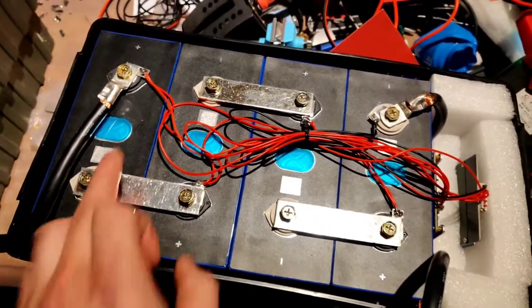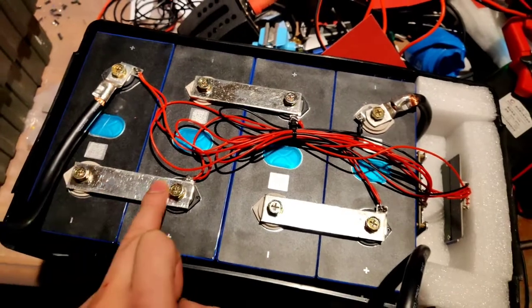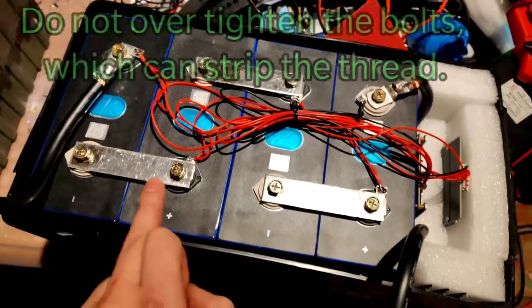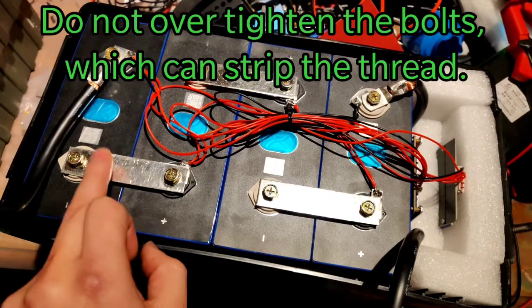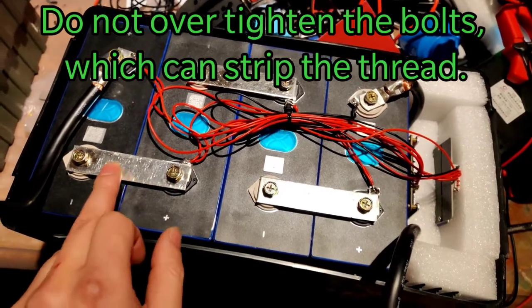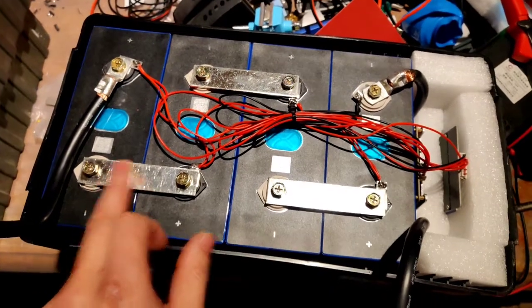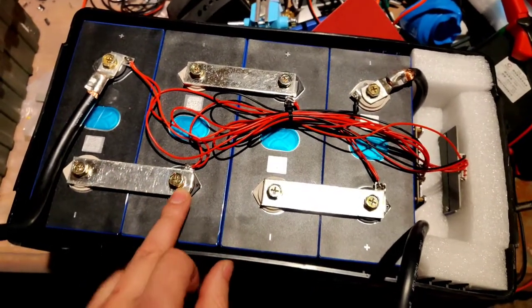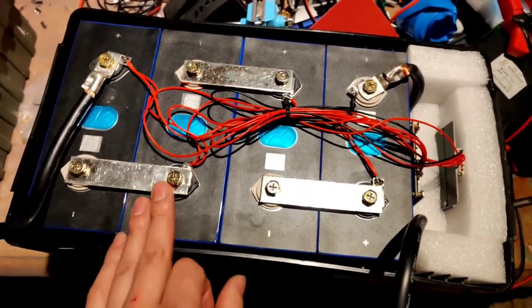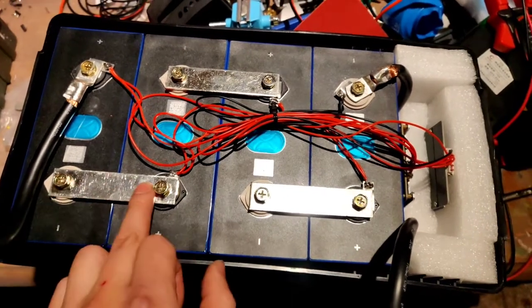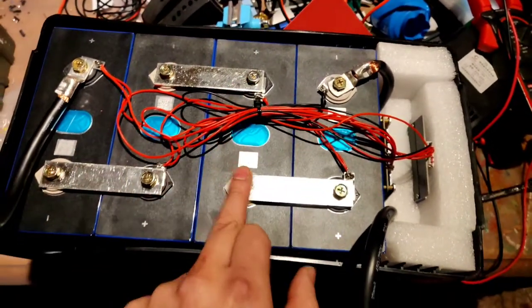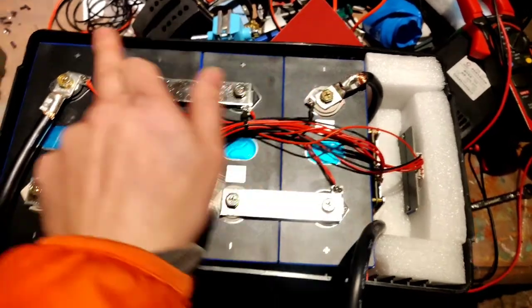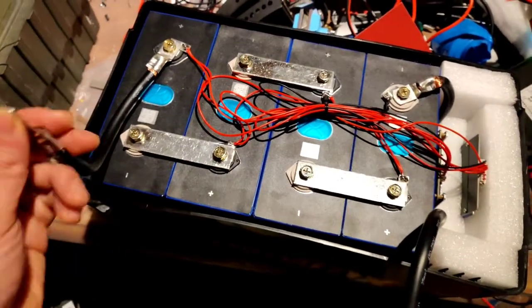So as you can see, that's the positive coming down here. These are the bus bars. Now these are copper bus bars. They look shiny and silver. That's because they've been nickel plated to completely not have any copper exposed, because copper will oxidize. So these are all protected with a layer of nickel, anodized or electroplated, however you want to call it. So it goes from here, goes up from here, comes from here, and that's your negative. That's your positive. Positive directly goes to the load, which is going to be over here.